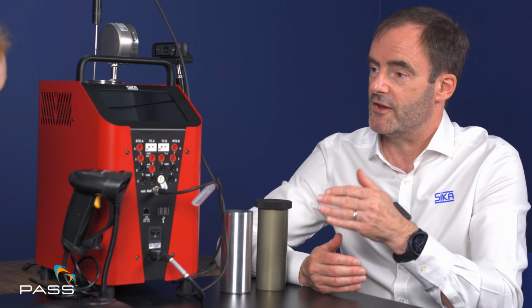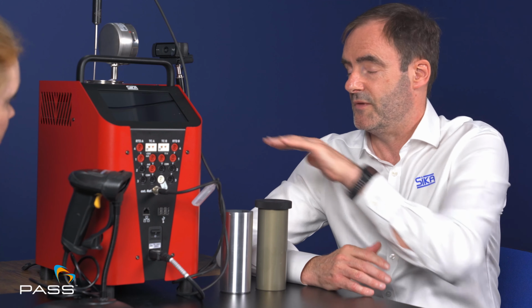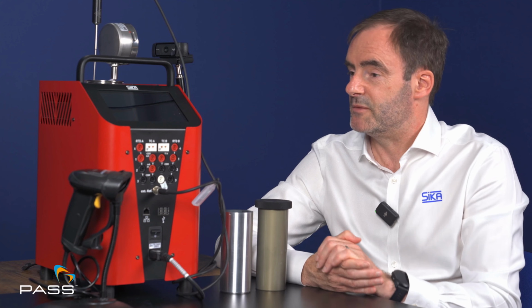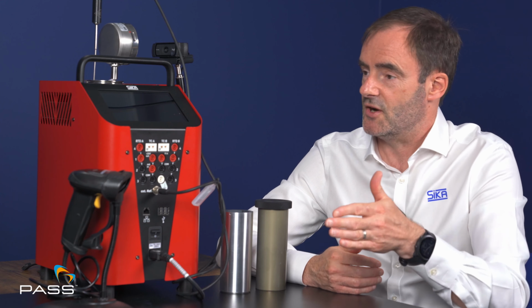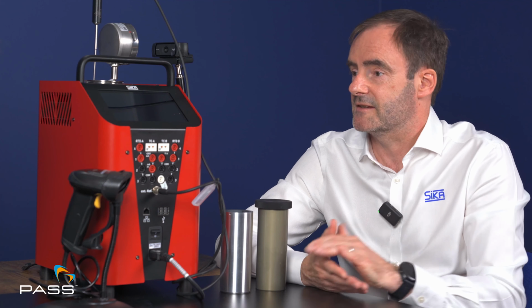If a customer has several hundred temperature sensors within their factory, the last thing they want is to have a lot of them leave the factory itself. So they want an on-site calibrator, where they can bring the temperature sensors to the calibrator or the calibrator to the temperature sensors and do the calibration on site very quickly. As we've said, it's 50% quicker to hit the stabilization points within the calibrator, so the downtime of the temperature sensors being used within the process is reduced significantly. So it might be more expensive initially, but you are going to save money over time if you invest in a Sika. When it comes to temperature calibration, time is a big factor, especially when you're looking to calibrate over wide temperature ranges, and it takes time to get to each of those temperature points. So time is money, and we can save that.